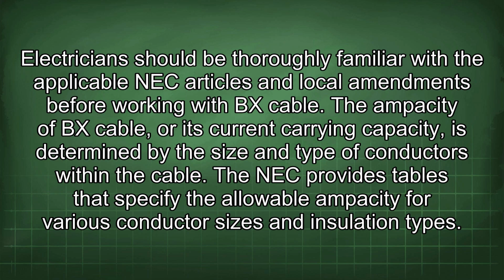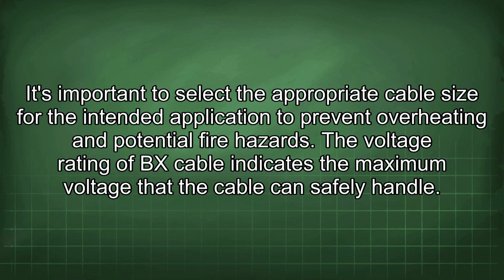The ampacity of BX cable, or its current carrying capacity, is determined by the size and type of conductors within the cable. The NEC provides tables that specify the allowable ampacity for various conductor sizes and insulation types. It's important to select the appropriate cable size for the intended application to prevent overheating and potential fire hazards.